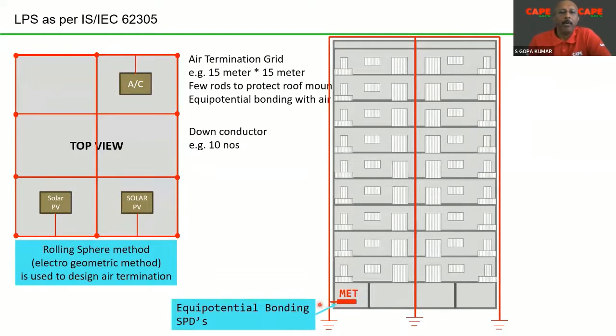Now, when we talk about equipotential bonding, the down conductor and the earth bus bar can be directly connected. But this earth bus bar and the phase and neutral conductors have to be equipotentially bonded through a device called an SPD, surge protective device. So basically, your lightning protection consists of an air termination, a down conductor, an earth termination, and an equipotential bonding system consisting of SPDs.